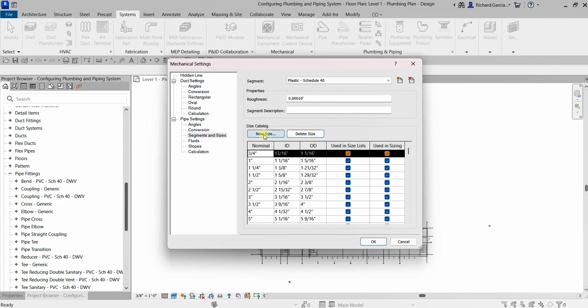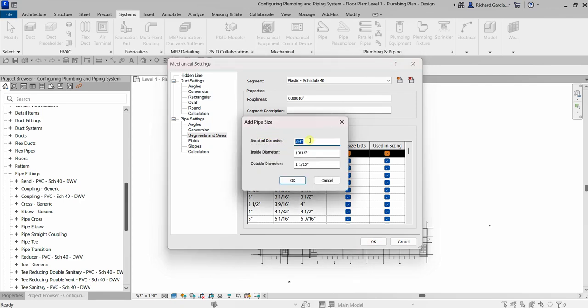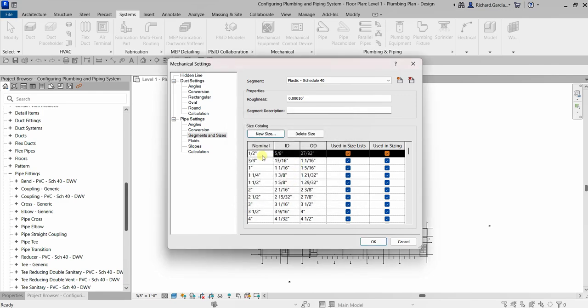Specify the size as 1/2 inch, the inside diameter as 5/8 inch, and the outside diameter as 27/32 inch, then click OK. As you can see it's now added for Plastic Schedule 40 — 1/2 inch. You can include this size in the size list and in the sizing by checking both checkboxes.